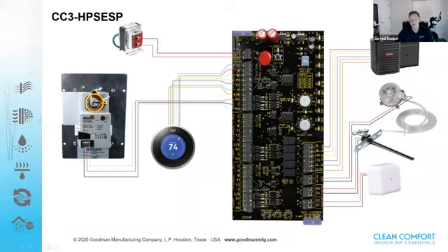You can use that feature. And what these are specifically for is locking out the heat pump when it's most efficient and least efficient. So for example, low balance point, I might say, hey, at 20 degrees, my heat pump is no longer as efficient as my electric or fossil fuel backup heat. So when we opt for second stage, I'm going to automatically opt for that conventional or fossil fuel backup heat.